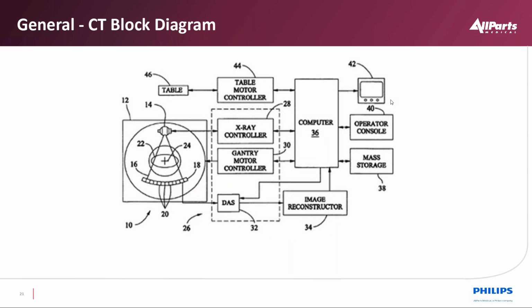Here is an example of a rough block diagram of a third generation CT scanner. There is the X-ray tube with the X-ray controller. The gantry is rotating, and we have to control that speed as we generate a view. As a reference point, we'll have an encoder as we rotate around, and that will trigger a sample from the data collection subsystem, DAS. From that, we take those views and transmit them to an image reconstruction subsystem that copies that raw data to a disk set, which later pulls it back in queue to reconstruct and then send a completed image to the computer.